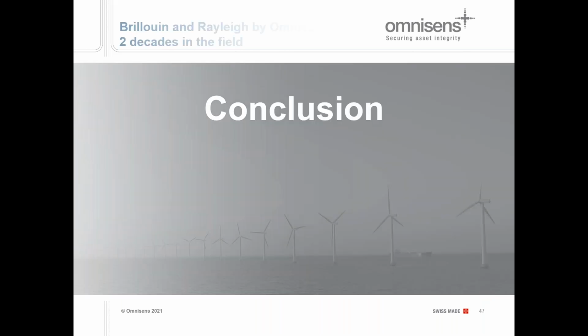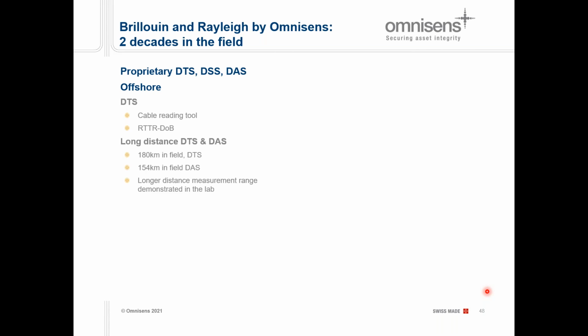I think it's about time to conclude. We've been working with Brillouin and Rayleigh for 2 decades in the field. It was fun and absolutely great. We now have proprietary technology for DTS, DSS, and DAS. In the offshore, we've seen that DTS can be used as a cable reading tool. It is also used more and more for real-time thermal rating and more depth of burial estimation. We have also seen that long-distance DTS and DAS are now possible, with 180 kilometers installed in the field for the DTS and 154 for the DAS, measuring in both directions, and longer distances have been demonstrated in the lab also. DSS is still in progress.